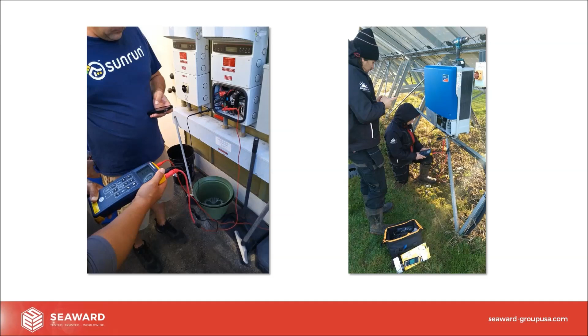We can also make better points of connection with a traditional PV tool. So you can see here on the left-hand side, our PV210, we're actually using our combiner box test leads. So here we've connected MC4s to an alligator clip, which can then be used in the bottom of the inverter, which you can see here on the left in a domestic property, and here on the right in a utility scale plant in a Sunny Boy. So we can make multiple points of connection that maybe a traditional tool cannot.